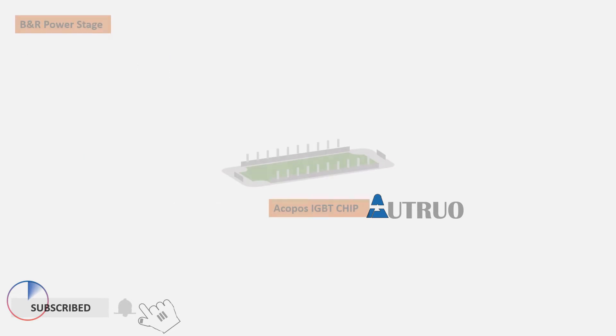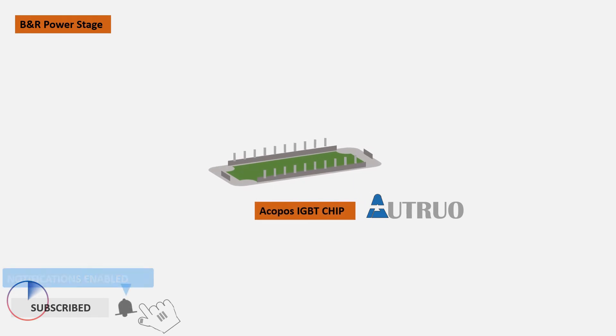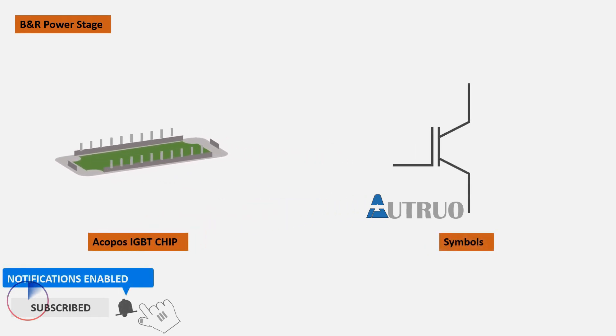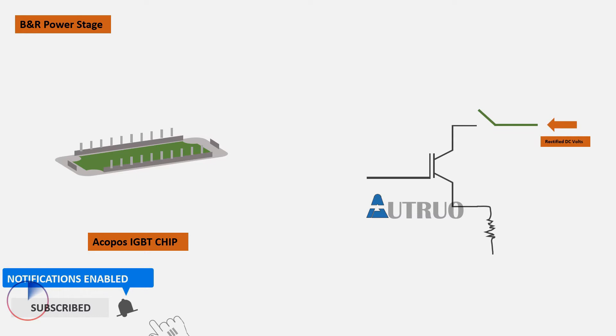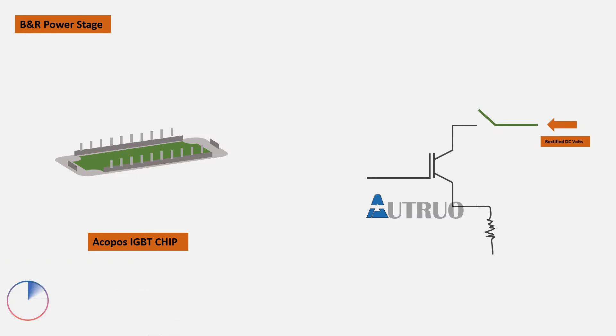A semiconductor device known as an Insulated Gate Bipolar Transistor, or IGBT, is a key component of the Acopos Multimodule inverter subsystem. These electronic devices are responsible for the power output of the multimodule. With the help of pulse-width-modulated signals, they generate an output voltage regulated in amplitude, frequency, and phase.